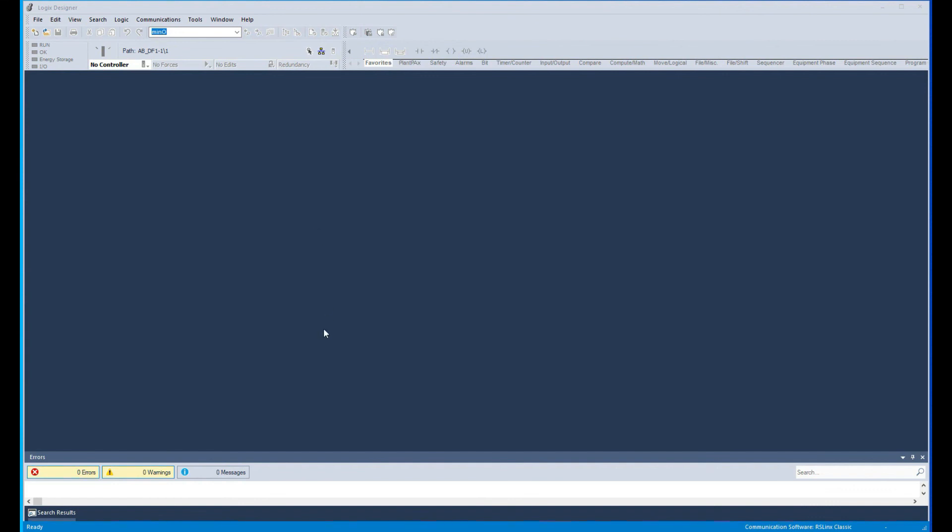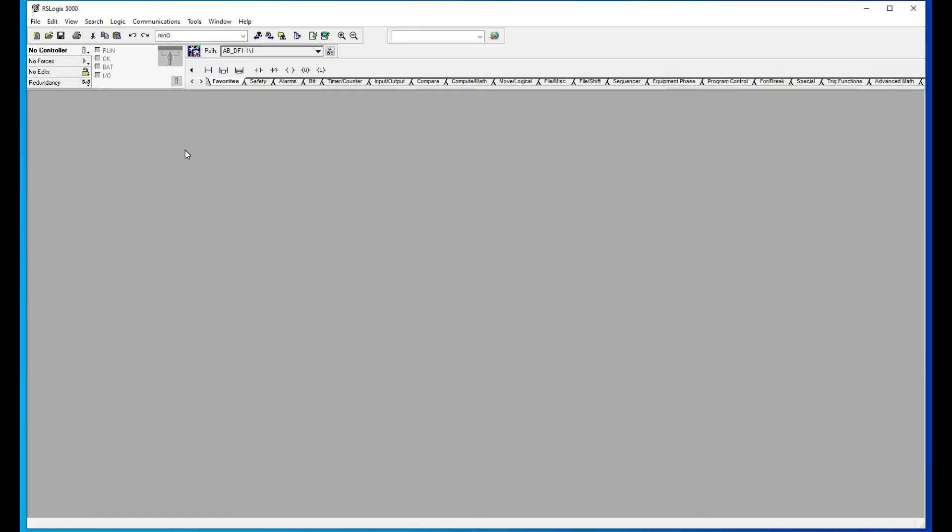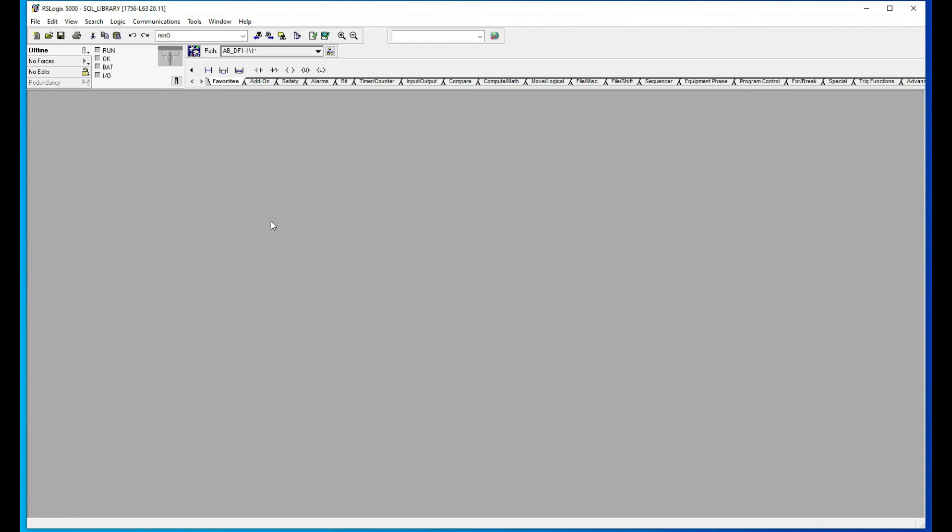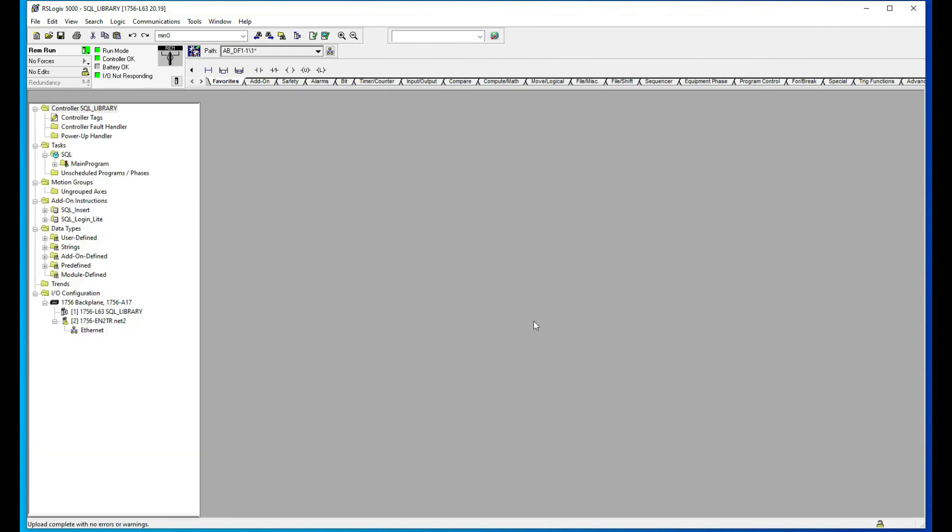And since we are using the L6 series, we cannot use Studio 5000 version 21 or higher. So as you can see here, the interface just changed because the highest version you can use with the L6 is version 20. That's why you saw the interface just change back to the RS Logix 5000 rather than the Studio 5000. I just wanted to show you that as well. So as you can see here, we are now online with our processor via the serial driver.